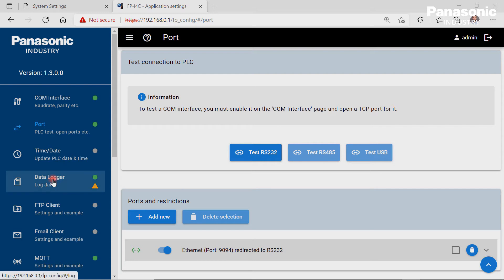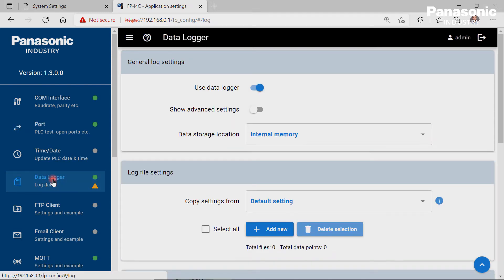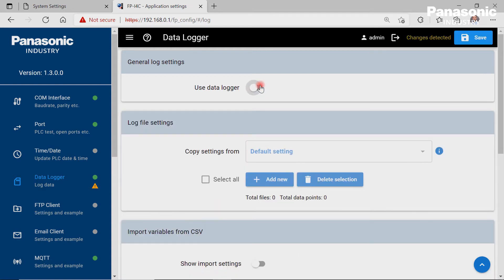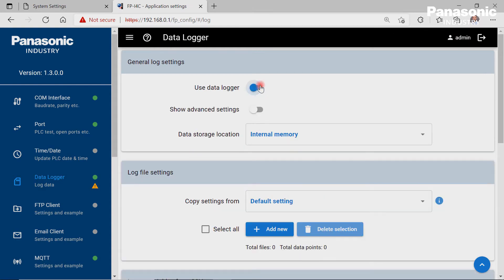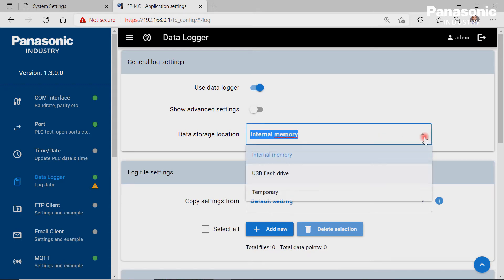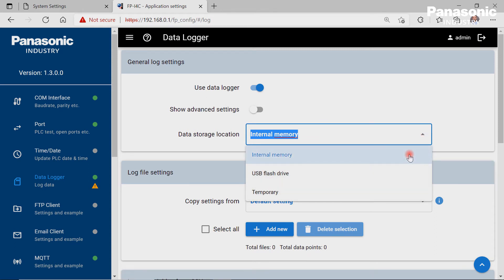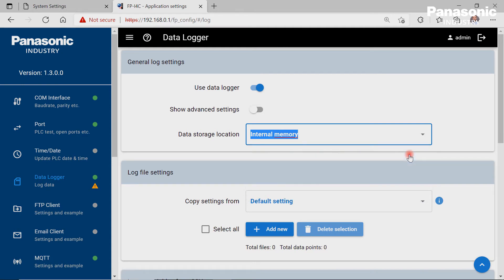The fourth step is to go to the data logger page to make the necessary configuration settings. In order to be able to log the PLC data, we need to enable the data logger first under General Log settings. As data storage location, we use the internal memory of the FPI4C unit. All the PLC data will be stored in a CSV file, which can be downloaded later from the FPI4C unit to our laptop in order to open it via Notepad or Excel.